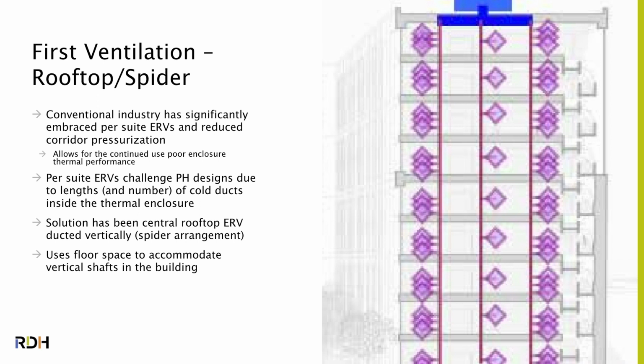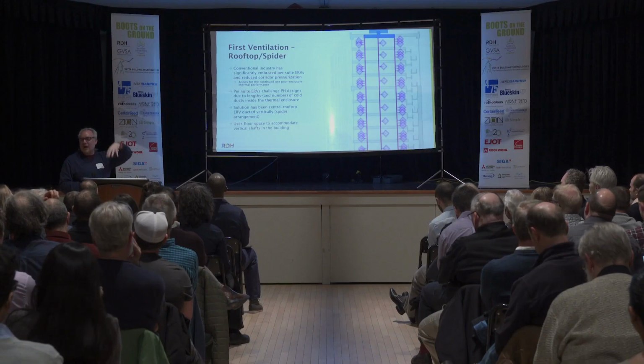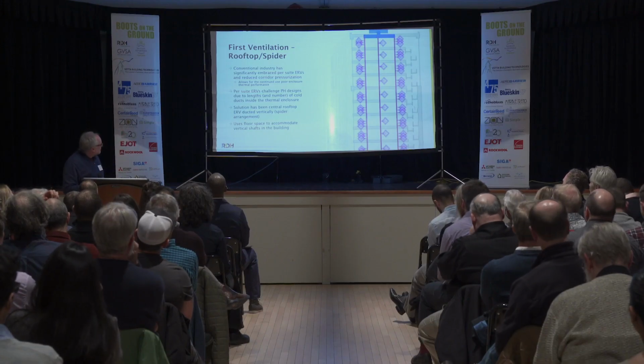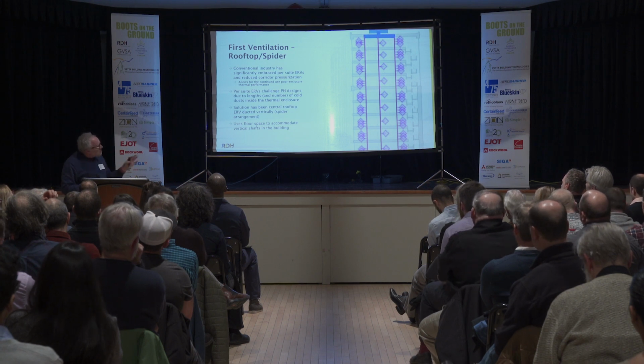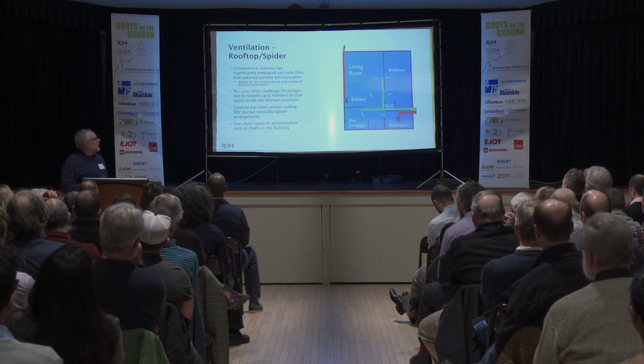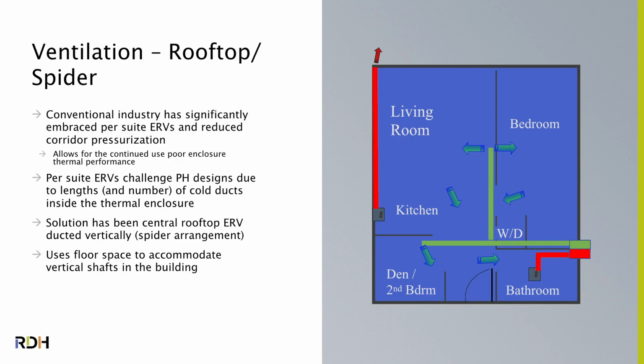Ventilation, what's been happening with passive house projects is most likely, especially in PHI, because that exterior duct is treated as part of the enclosure, on both the supply and exhaust side. Instead of going through an ERV in every suite, the pressure has been to put one ERV on the roof, spider it down, put in the ductwork. And that's what we've been mostly doing in most of our large passive houses. I have issues with that design, mostly because when people open a window in the cold weather, the stack effect immediately unbalances the system. So it was balanced on the day you balanced it, but as soon as people start using it, it's no longer balanced.